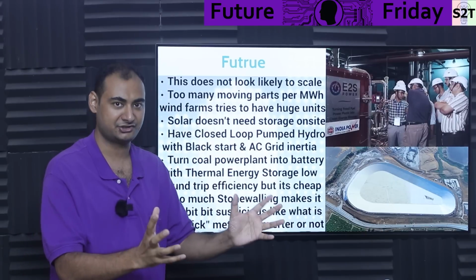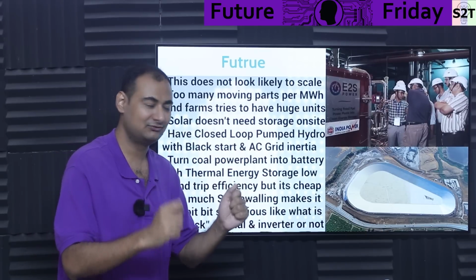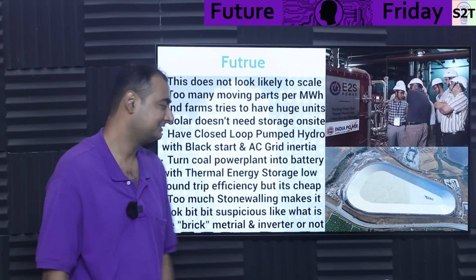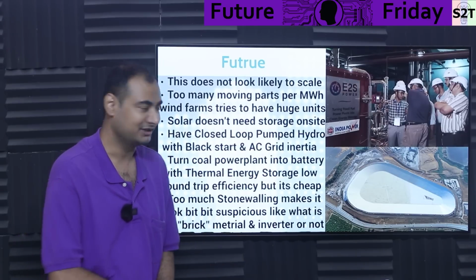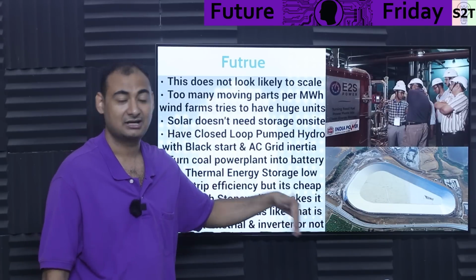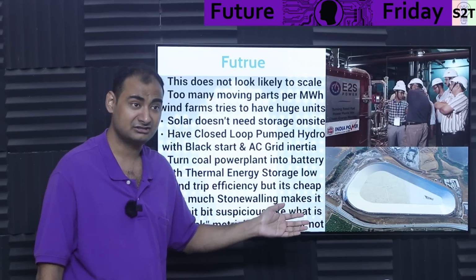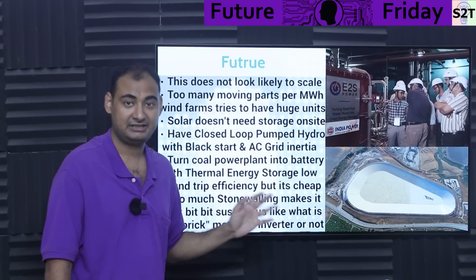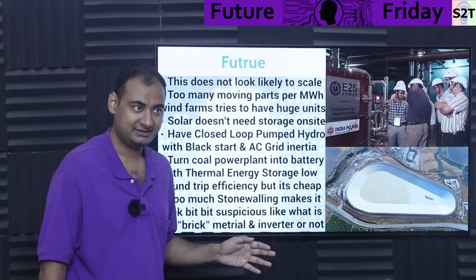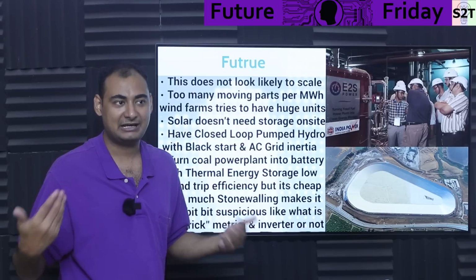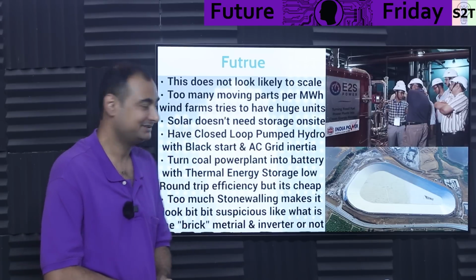It is actual inertia, meaning if you put load on or remove load, this puppy will tank it, which is exactly what you want. And how long will it last? Very long. What's the round trip efficiency? Surprisingly good. The old ones were 70%, modern ones are 80 to 85%. And because of the lifespan, it actually amortizes the cost, so you don't have to worry about it.